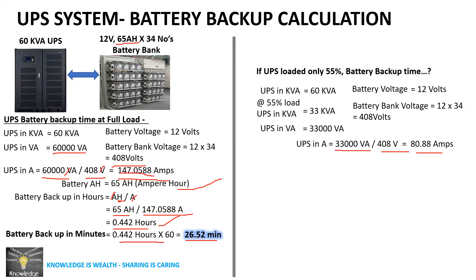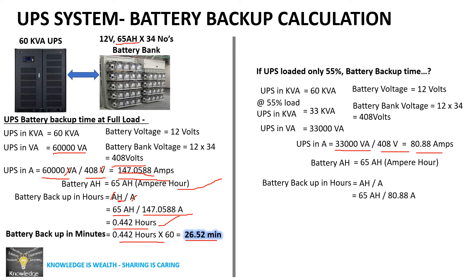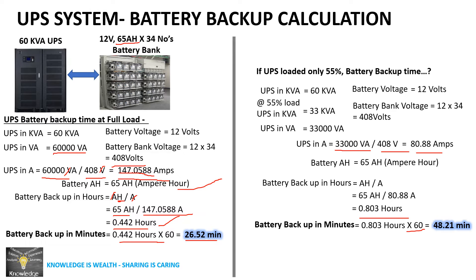To calculate the current at 55% load: 33,000 volt-ampere divided by 408 volts equals 80.88 amperes. Battery backup in hours: 65 Ah divided by 80.88 amperes = 0.803 hours. Multiplying by 60 gives 48 minutes. So the 60 kVA UPS working at 55% load, connected to the 65 Ah, 34-battery bank, will give around 48 minutes of battery backup.